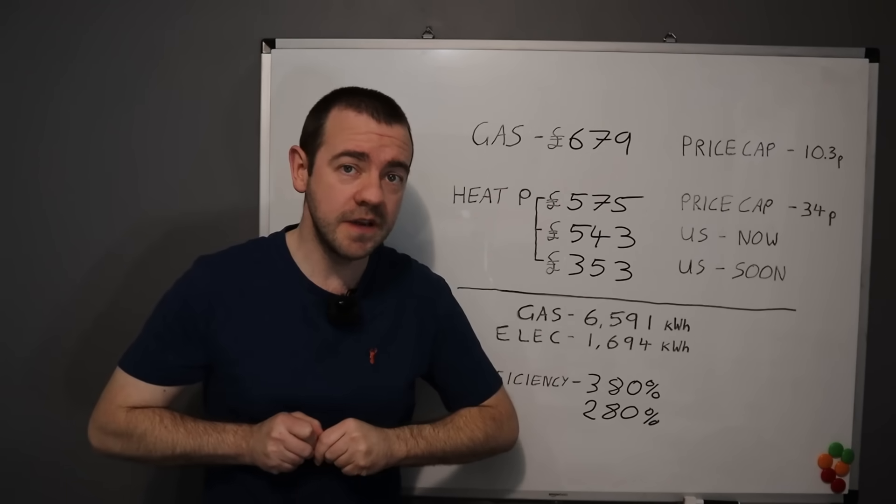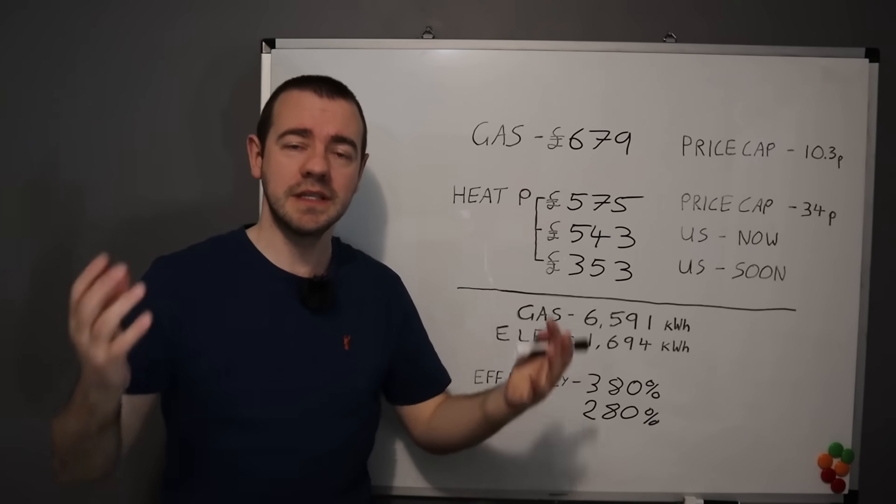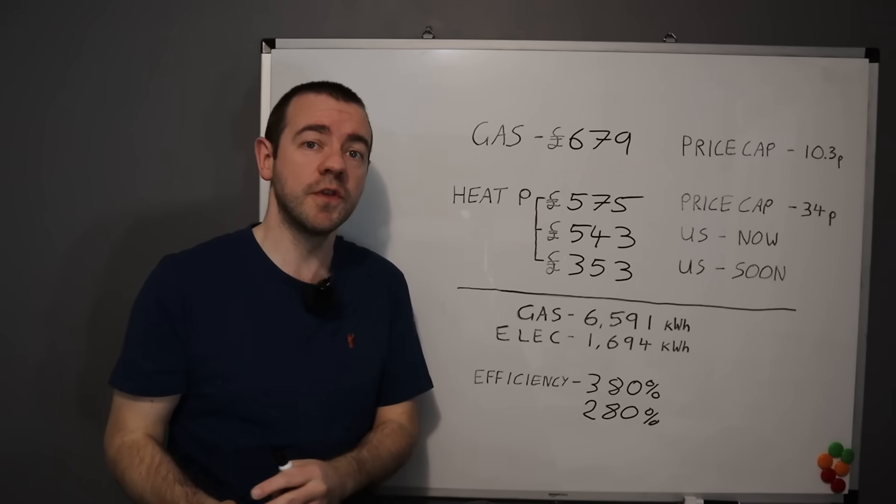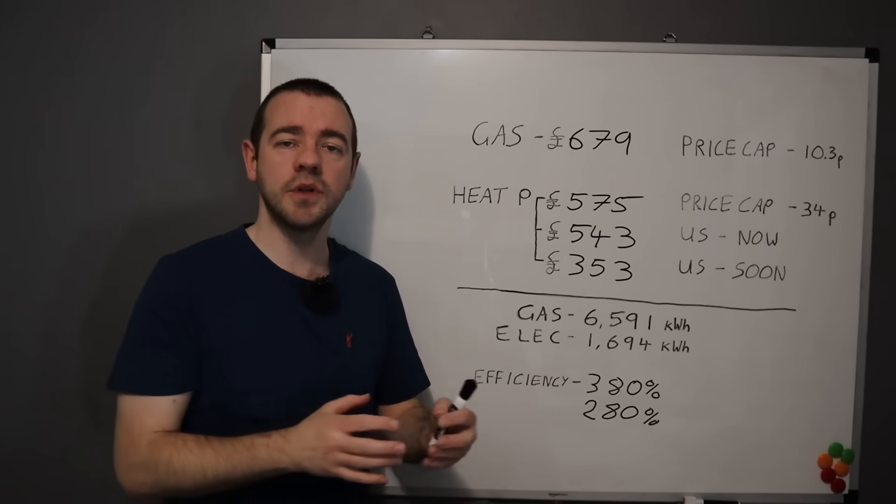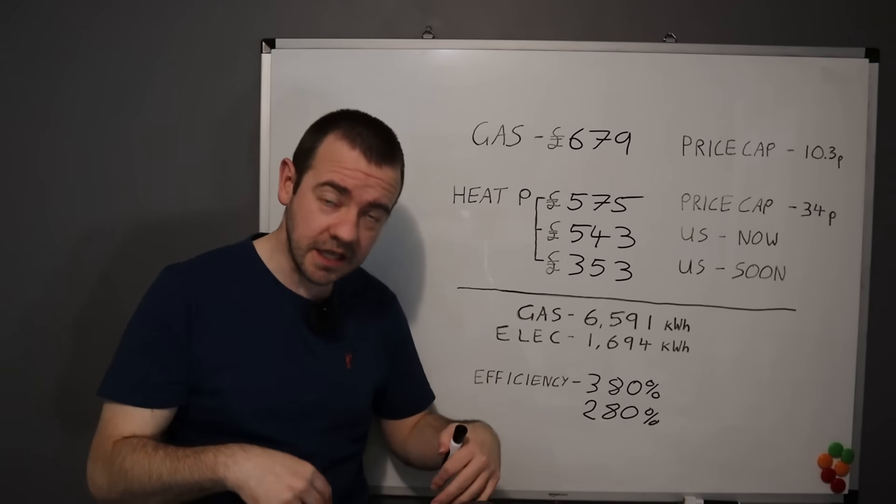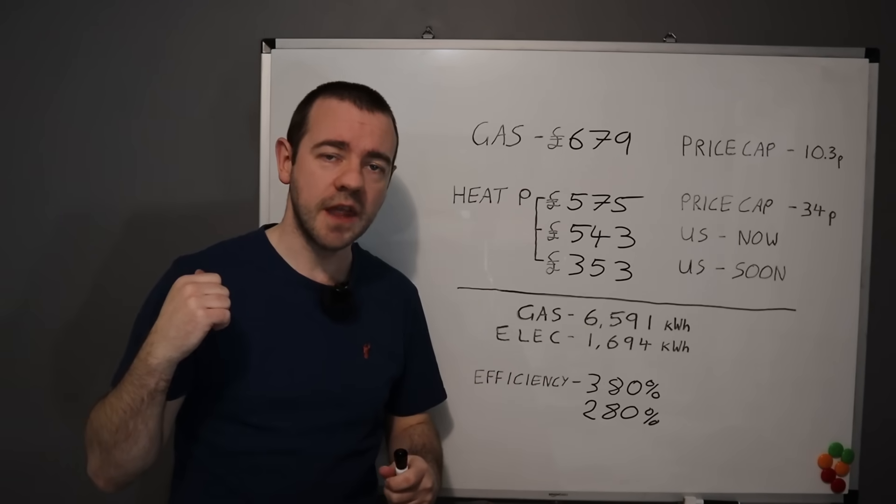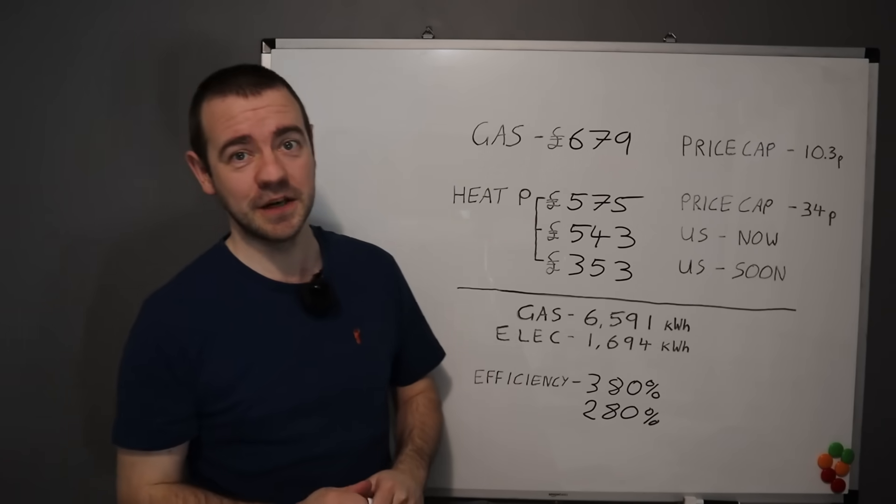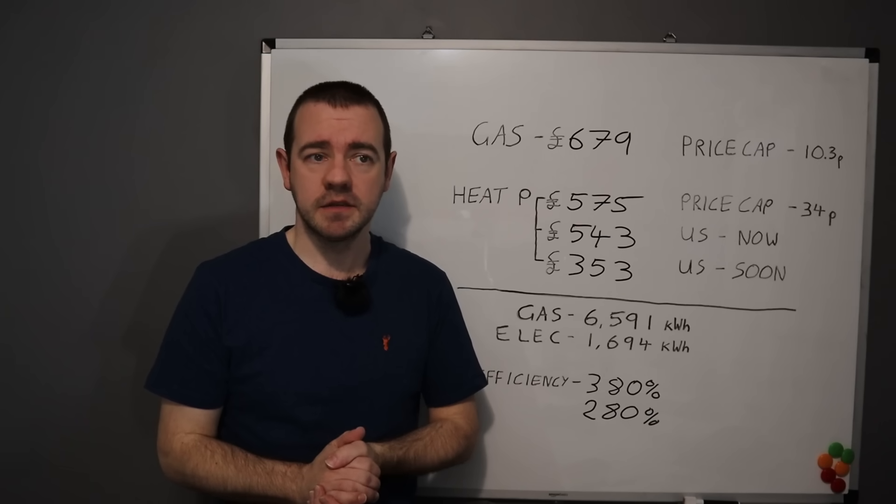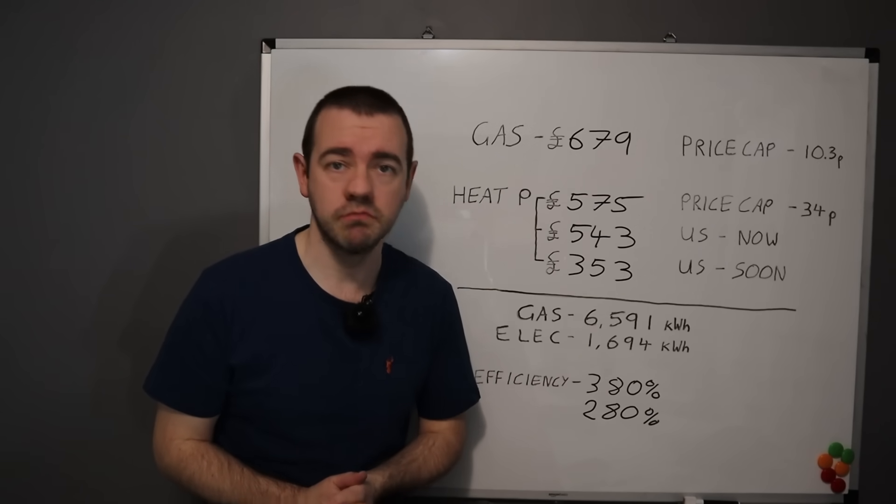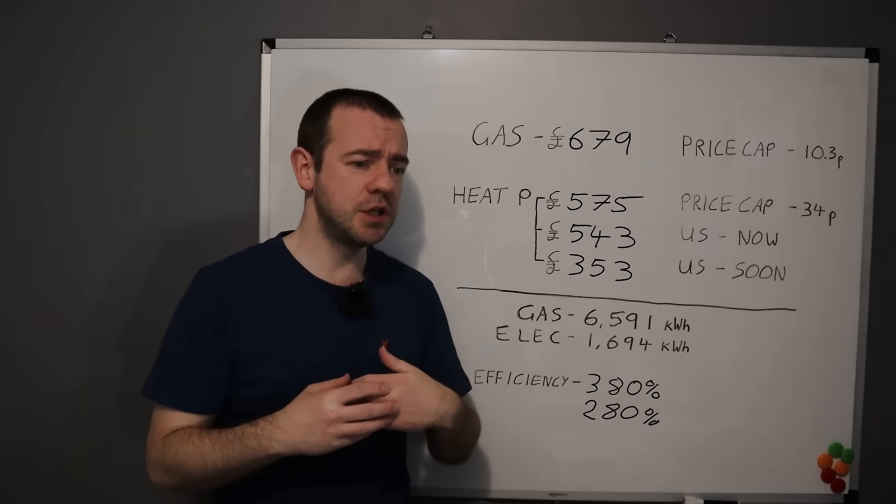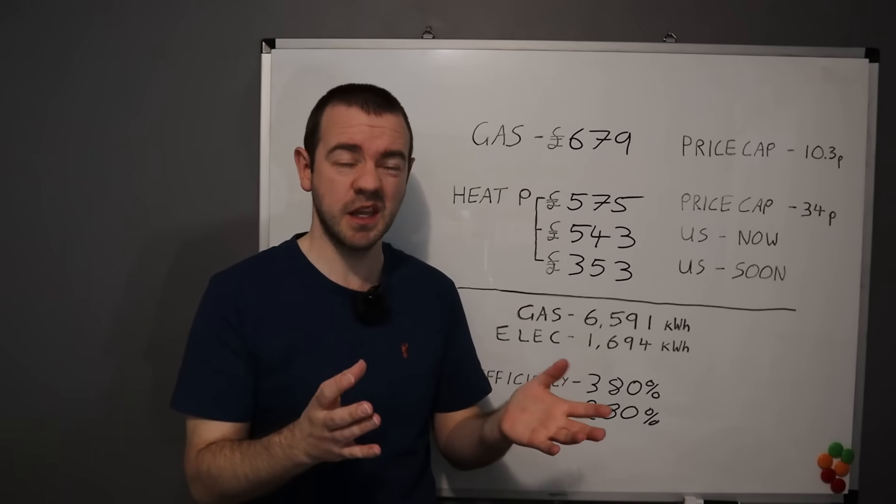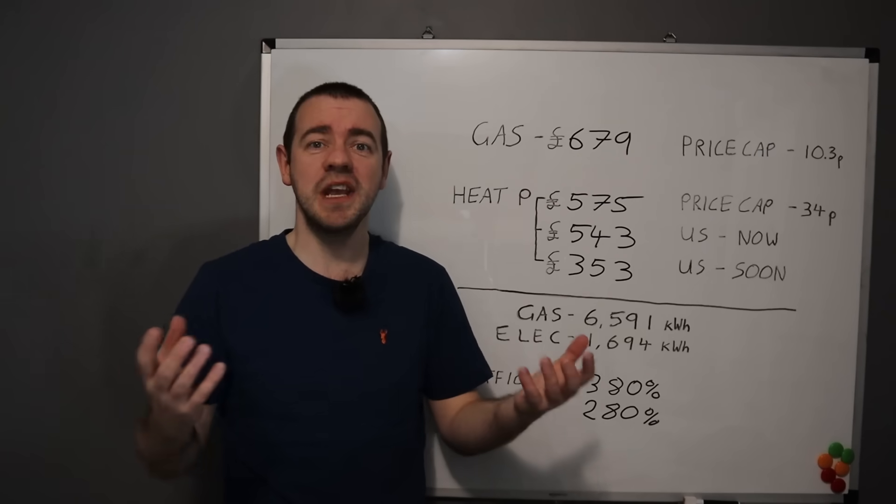So I can use all of that solar via the heat pump to get far more efficient use out of what is on my roof. So no, I won't be getting an eddy or anything like that. I did say I would show you how much we used on the worst day in terms of the electricity consumption. So this is on one of those, I think it was minus 13 to 15 during the night and about minus 11, 12 during the day. So again, for the UK, very, very cold. So you can see here, the month of December, the worst day for heating was 32 kilowatt hours worth of electricity. Again, that was really the coolest I've seen it for years. So this should be worst case scenario, 32 kilowatt hours.